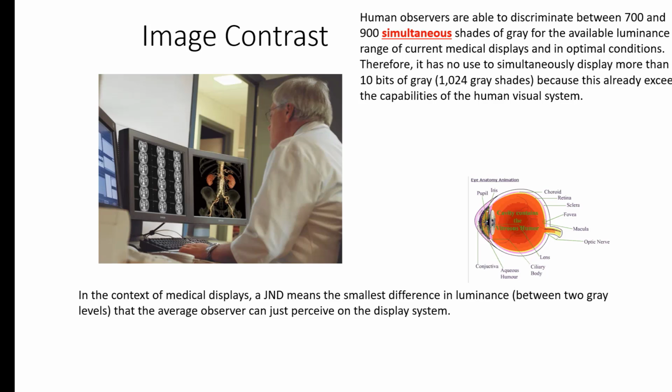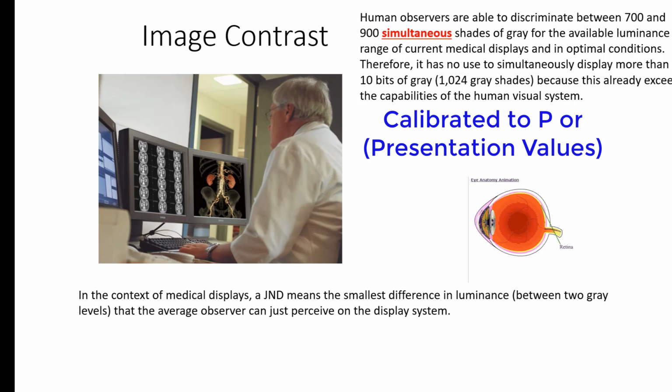So for diagnostic images and diagnostic monitors, we're using monitors that are, A, of a much higher quality, and B, more precise. But again, they are not graduated or calibrated on straight mathematics. They're calibrated on the human eye.